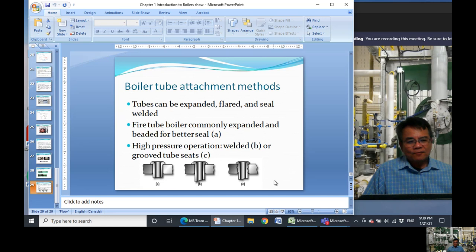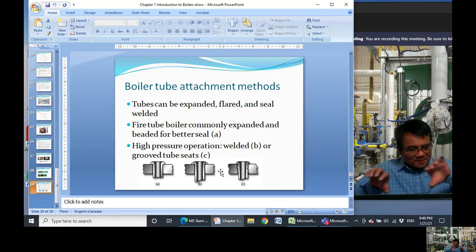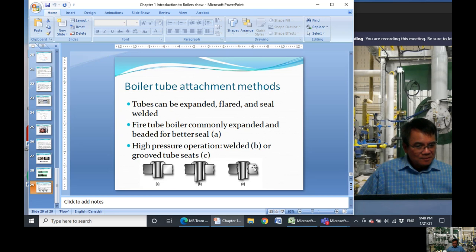Okay. Now, I've seen some of those, just like the water tube boiler tubes, and when I did an inspection there, the boiler had cooled down a little bit already, so they put in water that was not hot enough. And actually, the joint between the tube sheet and the tube itself got loose a little bit, and water came out. The first time I inspected this, I told the chief engineer, it seems like you have a tube leak. No, he said, it's always like this. But once you put the heat into there, when the tube expands, it will expand right against the metal, just like this piece of metal. In this case, it's not the tube seat, it is the drum housing. And when it expands there, it's quite tight, it's not going to leak.